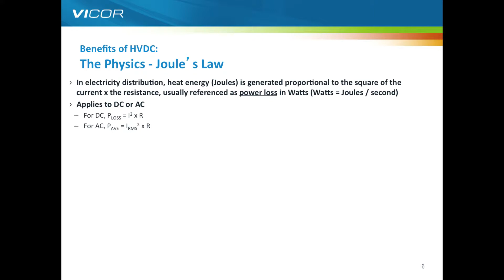Which means that for the same amount of power, if you can keep the voltage as high as possible and get it as close to the load as possible before you need to step down, you will have the most efficient architecture. In the drawing on the right, we have an AC through PFC system to 380 volts. If you drop down to 12 volts at that point, you're wasting a lot of power, and if your final conversion to 1 volt happens far from the load, you lose power again. But if you can maintain that high voltage, and use some new high power, high efficiency converters, you can save a lot of energy and have a much simpler system.